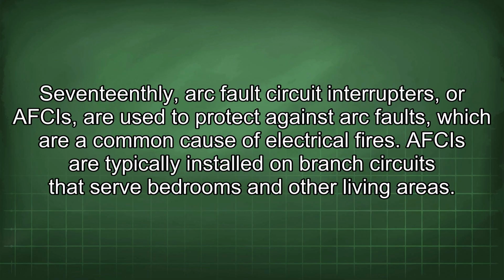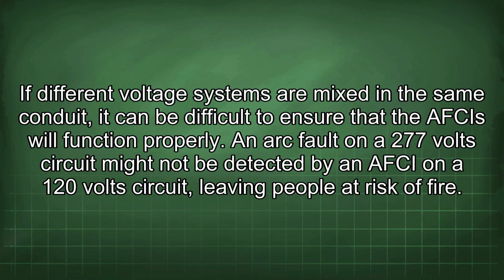17thly, arc fault circuit interrupters, or AFCIs, are used to protect against arc faults, which are a common cause of electrical fires. AFCIs are typically installed on branch circuits that serve bedrooms and other living areas. If different voltage systems are mixed in the same conduit, it can be difficult to ensure that the AFCIs will function properly. An arc fault on a 277-volt circuit might not be detected by an AFCI on a 120-volt circuit, leaving people at risk of fire.